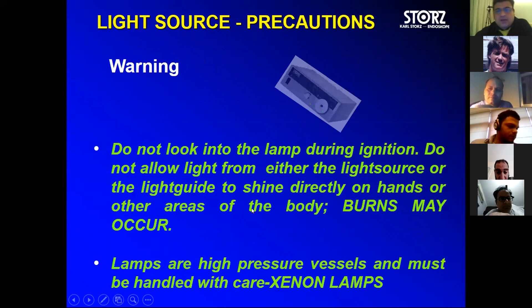Now, let's look at the light source. Most of the operation theaters across the globe have now very well accepted the xenon light source, which gives you 6000 Kelvin temperature, a true white light. Now, in layman's language, how do we get a good color? If this is my room, and if the room is dark and there is no light, then you cannot tell what is the color of my tie or what is the color of my shirt. So to see any object in the room, you need basically three things. You need luminance and you need chrominance.